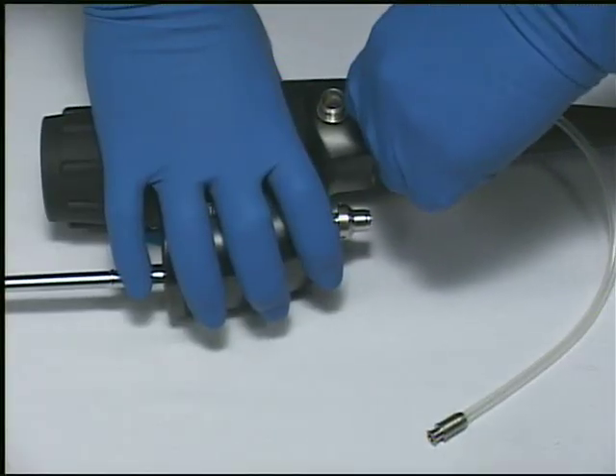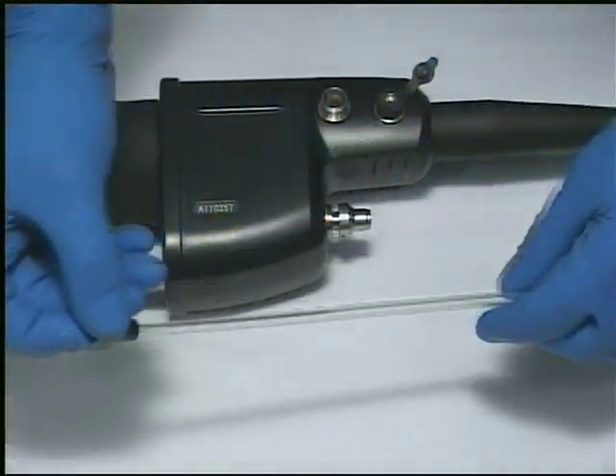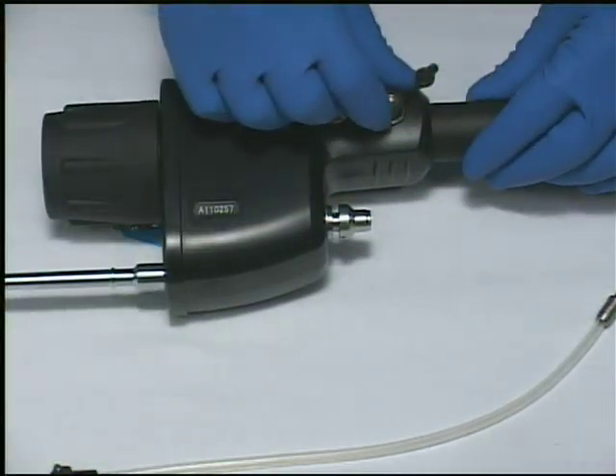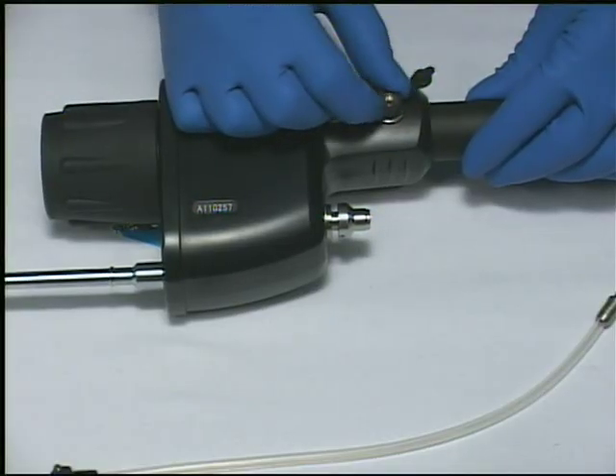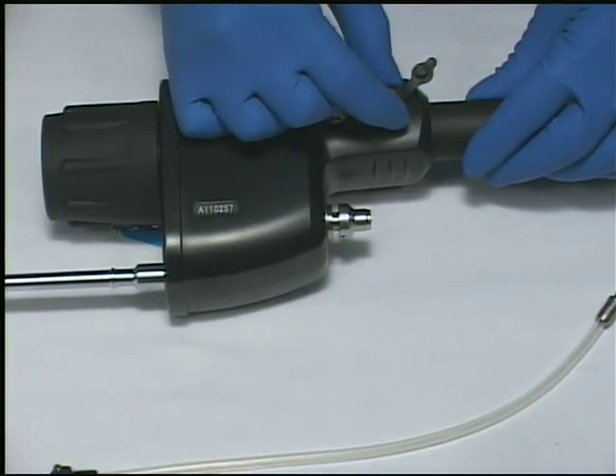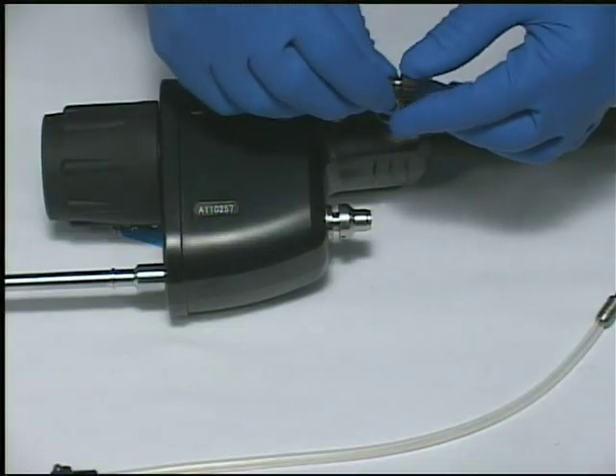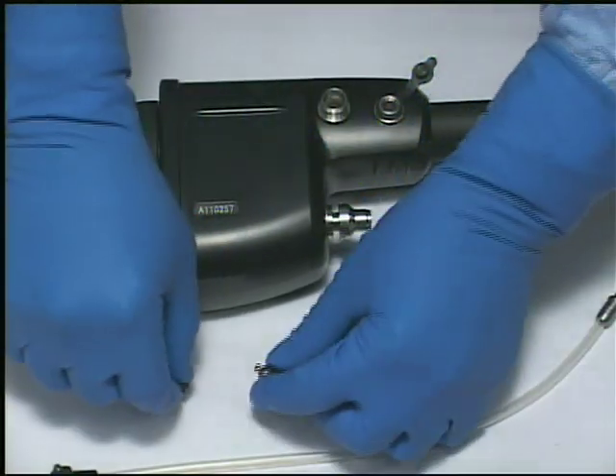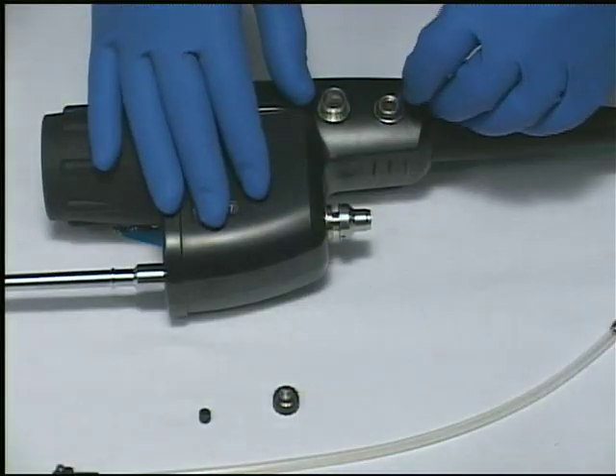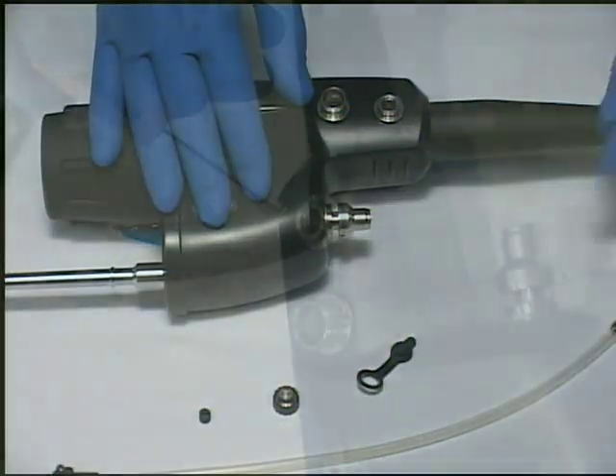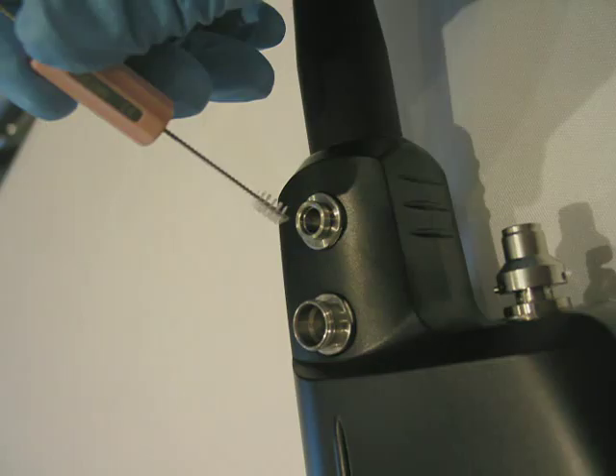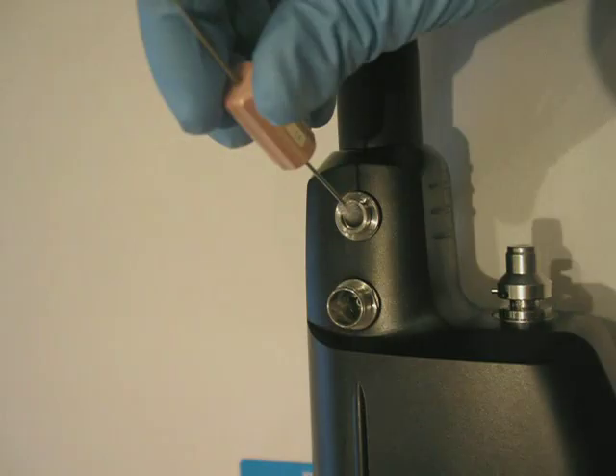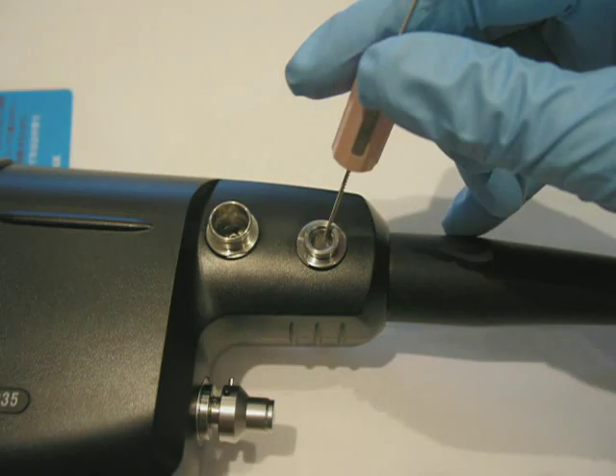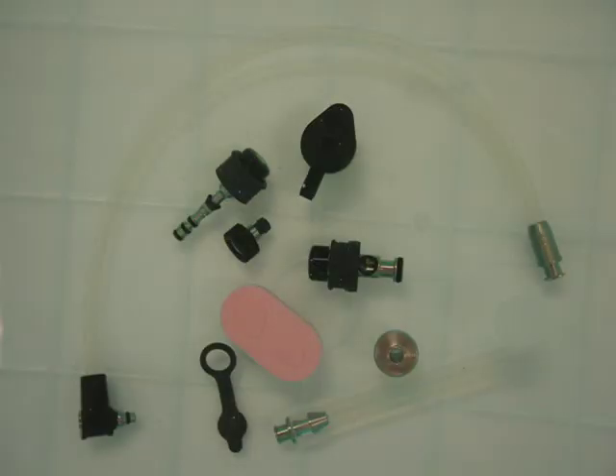During leak testing, remove the individual water jet components: OFB 113 irrigation tube, OEC12 water jet check valve adapter unit, and the OFB 118 connector cap as illustrated. Use the CS-C8S cleaning brush to scrub clean the inside walls of the water jet cylinder on the endoscope PVE connector. Manually brush clean each individual component using the CS-C8S brush.